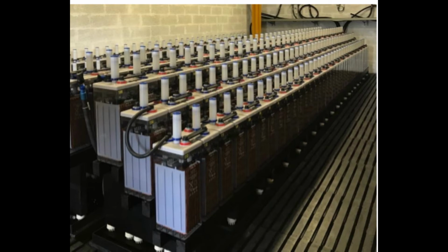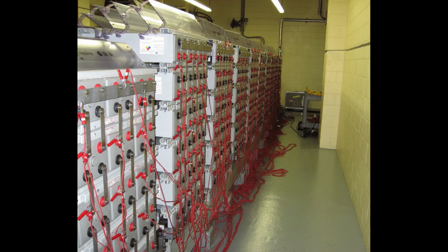However, if it is a VRLA battery with individual cells in steel trays or cans, it can be a little more complicated in locating and then eliminating the path. Obviously, the first step is going to be the same. You have to look closely at the area where the cover of the cells is in contact with the tray.